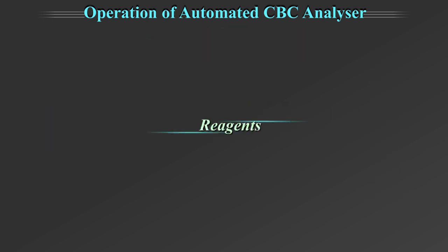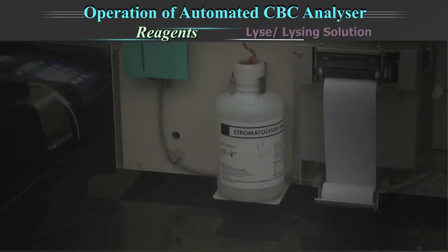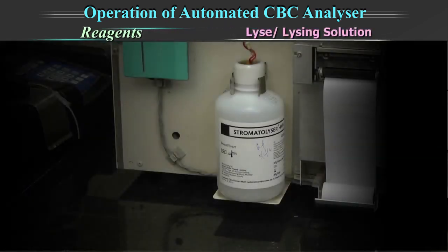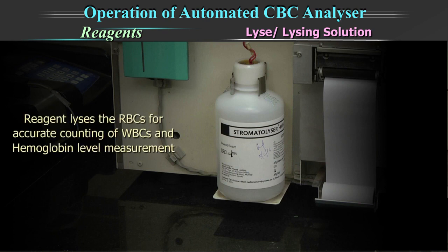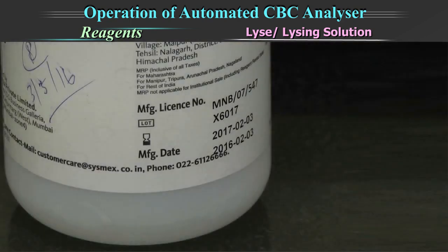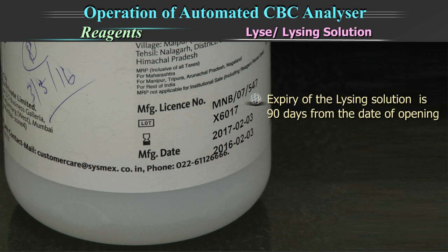Reagents used in this machine. Lysing solution, for example, Stromatolyser. This reagent lyses the RBCs for accurate counting of white blood cells and hemoglobin level measurements. In this case, the expiry of the lysing solution is 90 days from the day of opening. Please check expiry of reagent on the label or from your manufacturer.